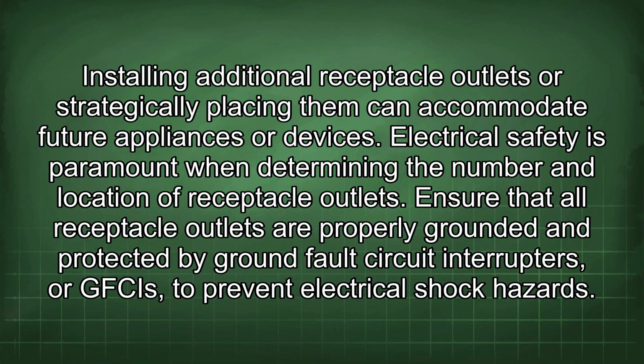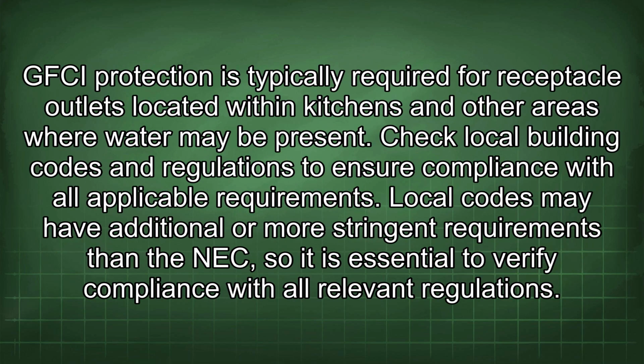Ensure that all receptacle outlets are properly grounded and protected by ground fault circuit interrupters, or GFCIs, to prevent electrical shock hazards. GFCI protection is typically required for receptacle outlets located within kitchens and other areas where water may be present. Check local building codes and regulations to ensure compliance with all applicable requirements. Local codes may have additional or more stringent requirements than the NEC, so it is essential to verify compliance with all relevant regulations.